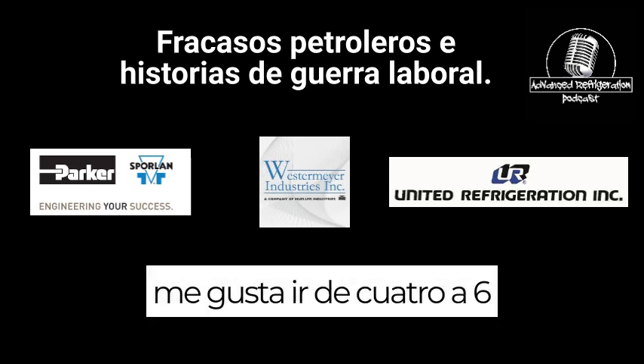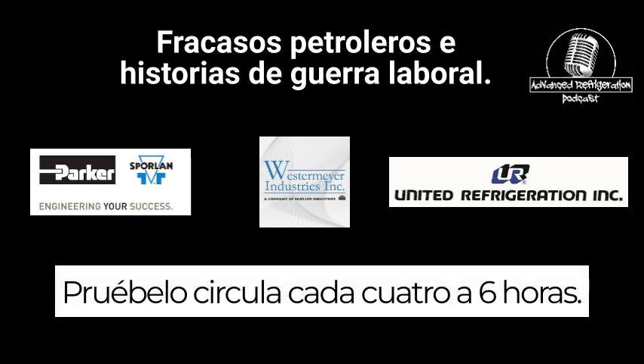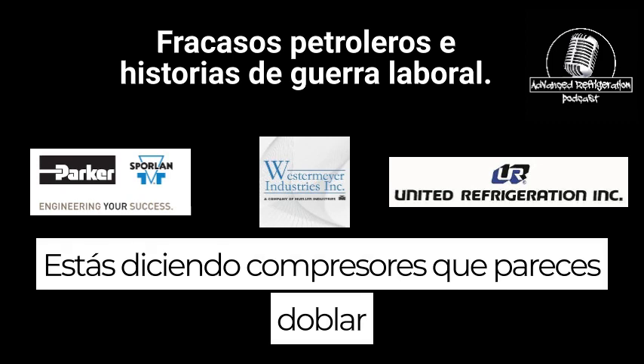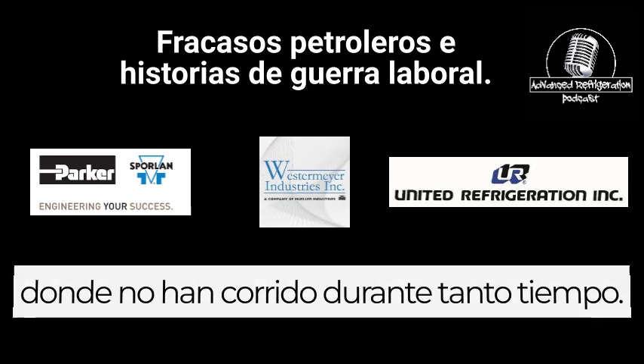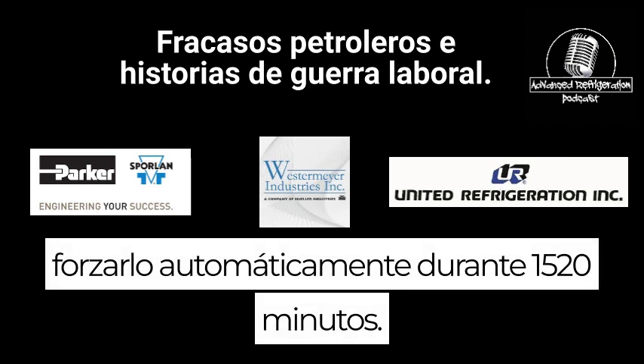I like to go 4 to 6 hours, depending on what my load is, to try to circulate some of that oil in every one of those compressors. So, you're saying if I have an oversized rack, compressors that haven't run for that long, basically you'll have them forced on. The controller will automatically force it on for 15, 20 minutes. Is that correct?